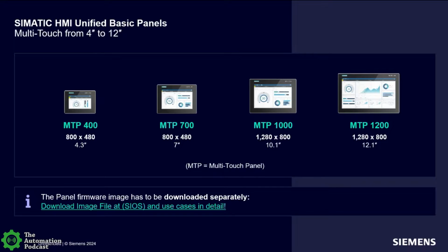On our support site, we'll actually release an update image, and in your TIA project, when you update your software, you'll have an option to go through a change device and say, I actually want to use the version 19 update 1 image. And then you can configure that device to that panel image. So you can freeze it at the level that it's currently at, or you can continue to rev it up as you move further down in the software as well.